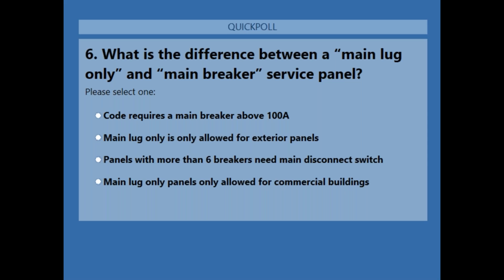The main breaker has that main switch up at the top of it. Main lug doesn't have that switch. The conductors just come in and land on the top. They're a little bit cheaper because you're not buying that 200 amp breaker, that main switch that's up at the top of it. So when can you avoid that cost and get the main lug only panel versus when do you need to buy the one with the switch itself?